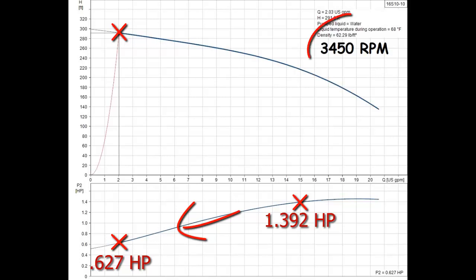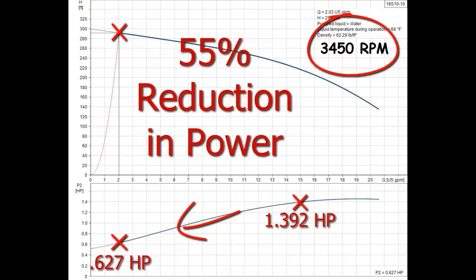That's right, the pump speed or RPM stays at the normal 3450 RPM while the energy consumption drops by 55% when simply restricting the flow with a valve.